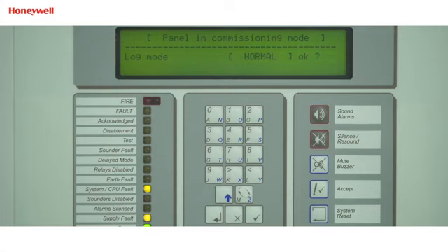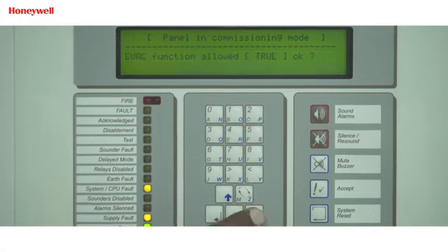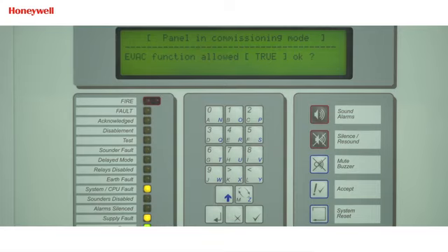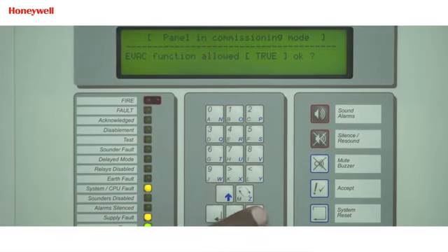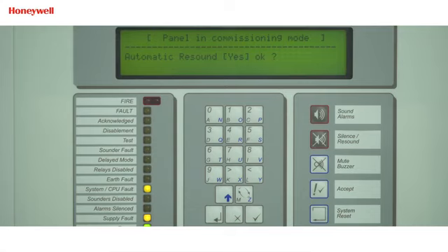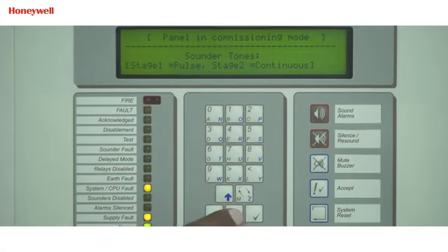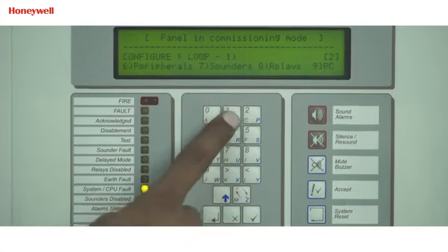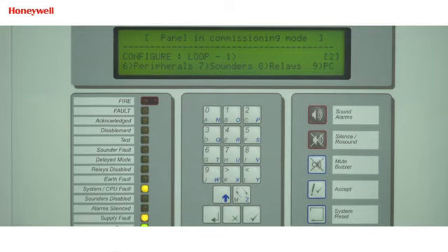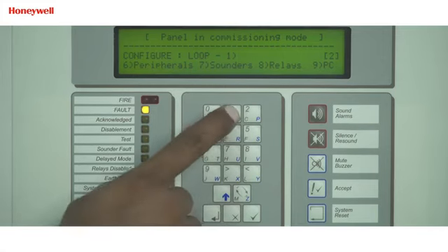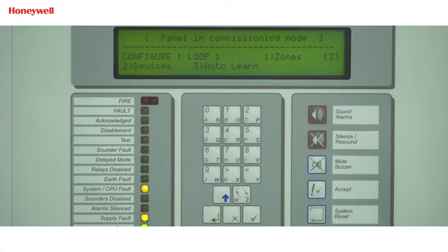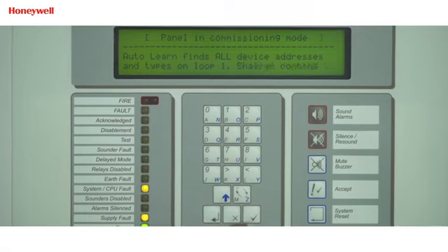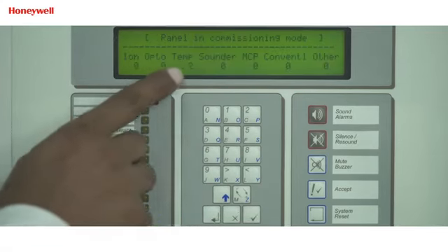Log mode, normal. Hit tick mark to go to next screen. Allow evac function, yes. Hit tick mark to go to next screen. Allow resound function, yes. Hit tick mark to go to next screen. Now press cross mark button and go to configure by pressing key 1. Now we must select the loop as we have installed only one loop. So we are going to select loop 1 by pressing key 1 and then auto learn by pressing key 3. It will show the number of detectors and modules connected to system.